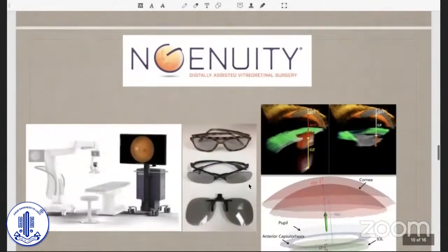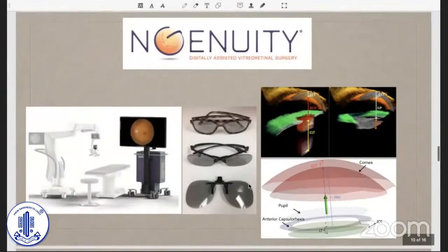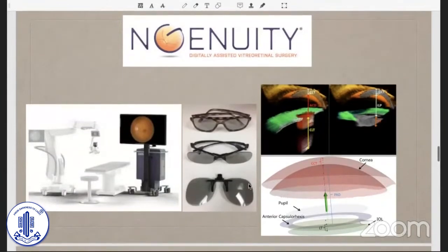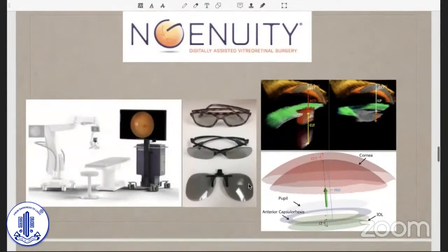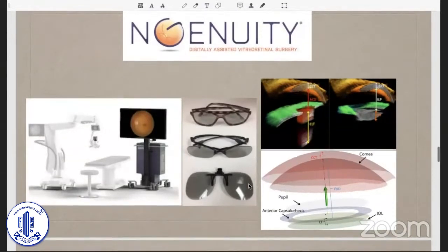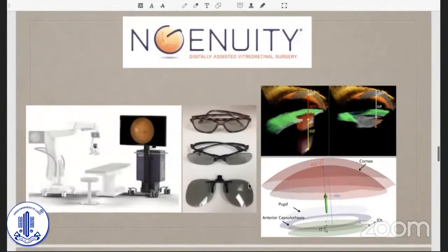This is how the Ngenuity works. It consists of the 3D camera which is attached to any regular microscope, and that captures the image and sends it to the processor, and the processor in turn displays it on the monitor in 3D. Then we have to use the Polaroid glasses to get the effect of the three-dimensional image. Next slide.